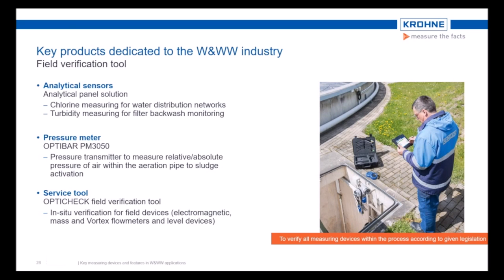Last device within that chapter is a verification tool, which makes it possible to verify the devices, especially the MAG meters. This is often required by legislation within a certain period, so the user can connect the tool to the field device and check if all internal parameters still meet the requirements or if maintenance needs to be carried out. So even the accuracy can be verified with such a tool. All tested parameters will be stored and documented within a protocol to be printed, emailed or stored accordingly. So this handheld verification tool is of course suitable to be used outside even when you have a rainy day.